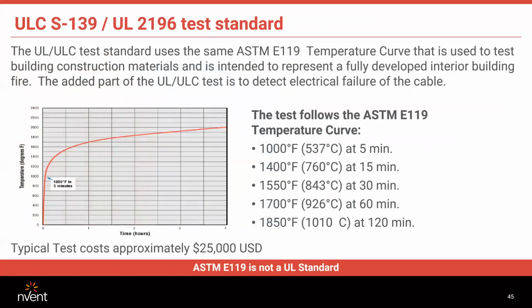The test is done per the ASTM E119 time temperature curve. That's basically an American standard test measurement, and it simulates the rise in a real life fire. So for the first 5 minutes, you're going to go from 0 to 1,000 degrees Fahrenheit. After about a half hour, you're going to be up over 1,500 degrees. And the test maxes out at 1,850 degrees after 2 hours.